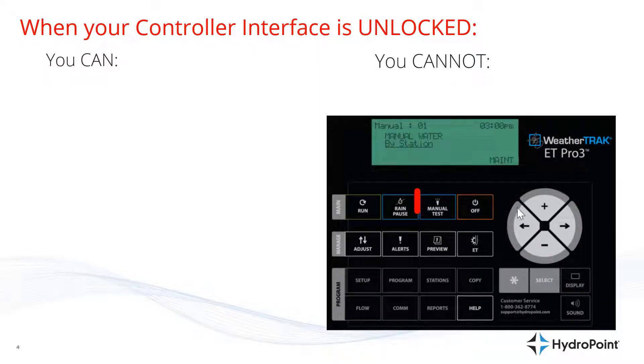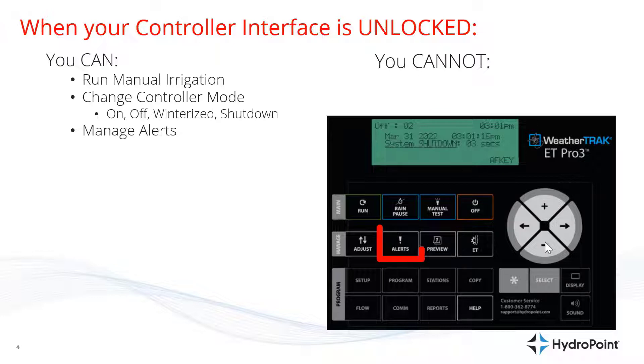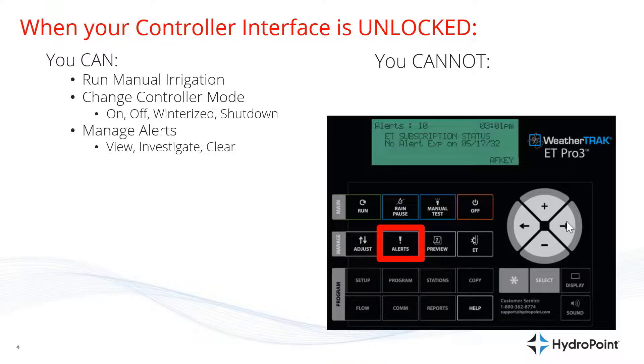We're focused on the maintenance features, so it's important that you can run manual irrigation, test your system, and run wet checks in the field. You can also change your controller mode — turn your controller on, off, to winterized, or shut down. When a controller is unlocked, you can also manage alerts, meaning you can view any alerts you have, investigate which stations or what details the controller knows about your alerts, and clear those alerts.